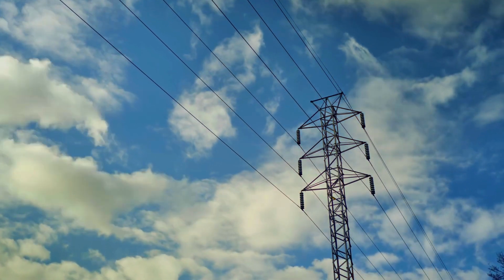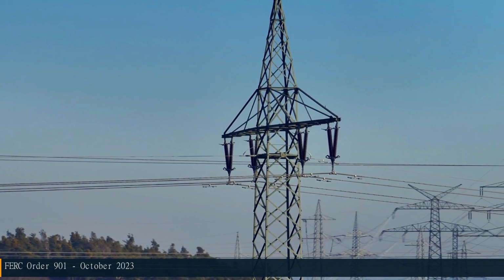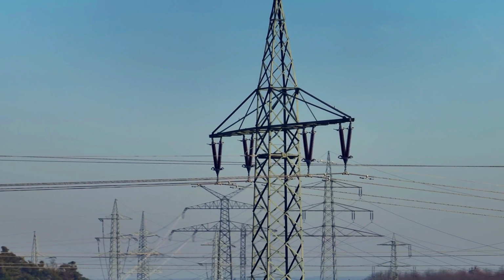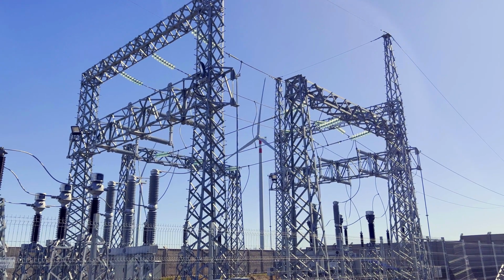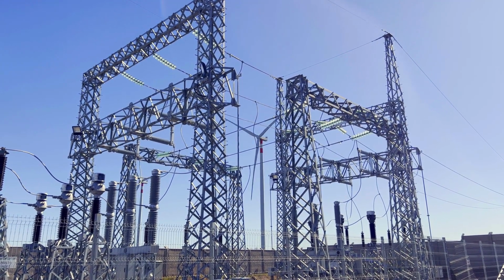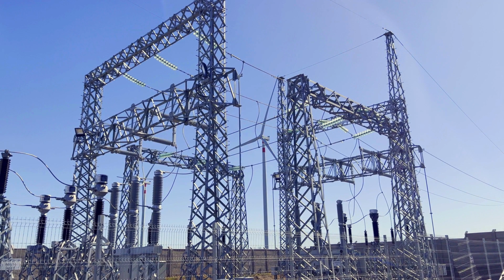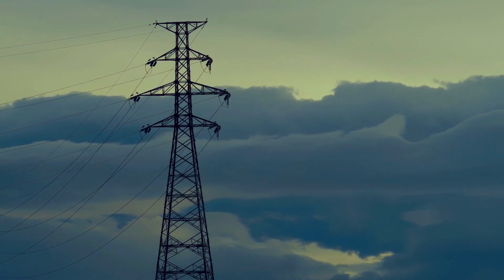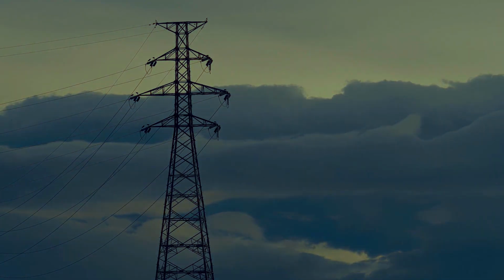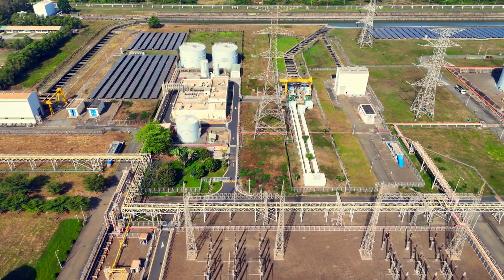In October 2023, FERC issued Order 901, directing NERC to develop a comprehensive set of reliability standards for inverter-based resources over 3 years. The requirements cover ride-through performance. Inverter-based resources must stay connected during voltage and frequency disturbances rather than disconnecting. Data and model validation. Utilities must demonstrate how their inverters actually behave in abnormal conditions, which many currently cannot. And planning standards. Interconnection studies must account for IBR characteristics, not just assume they behave like the synchronous machines they're replacing. The deadline for the planning standards is November 2026.